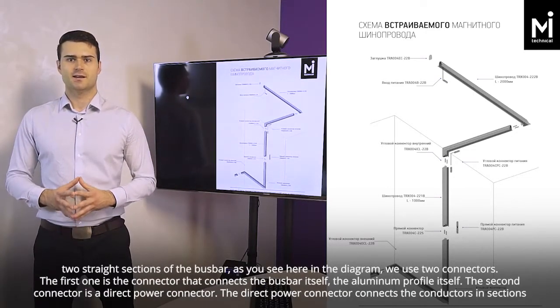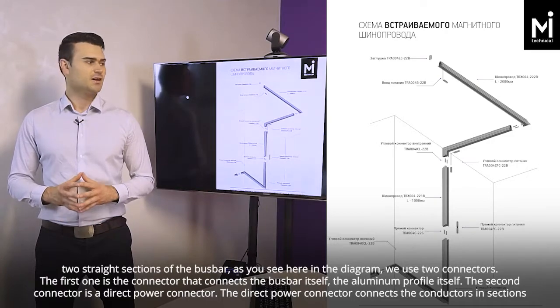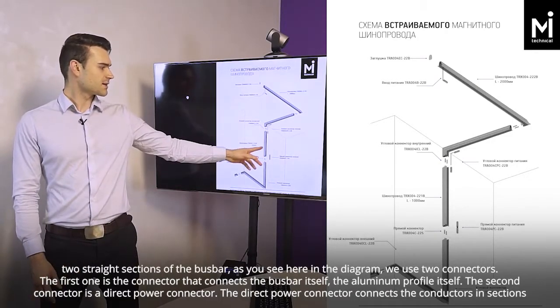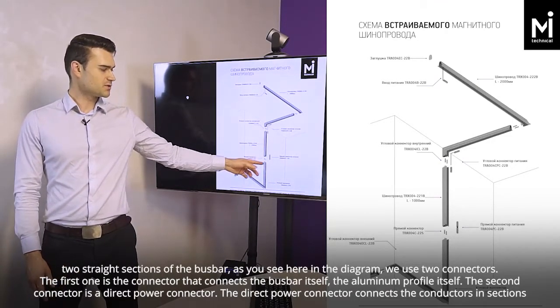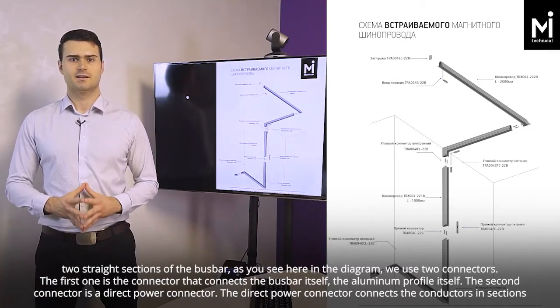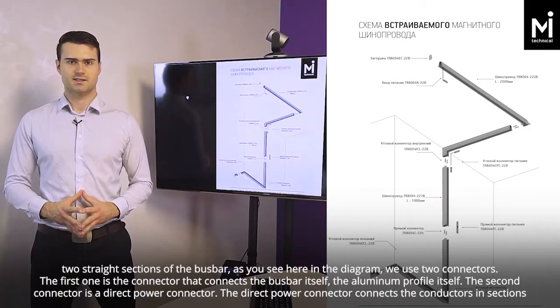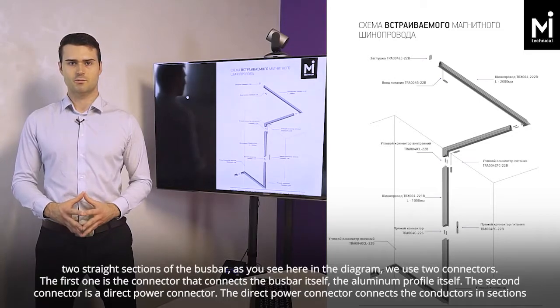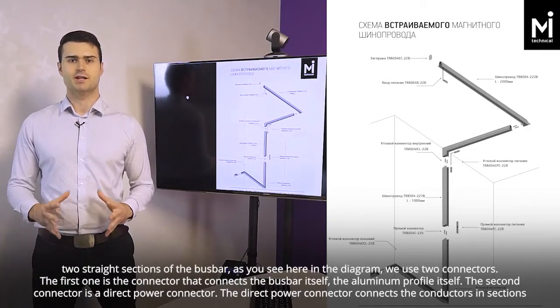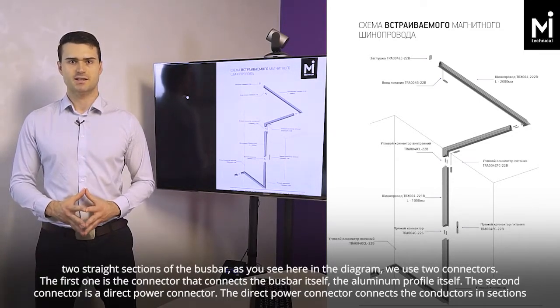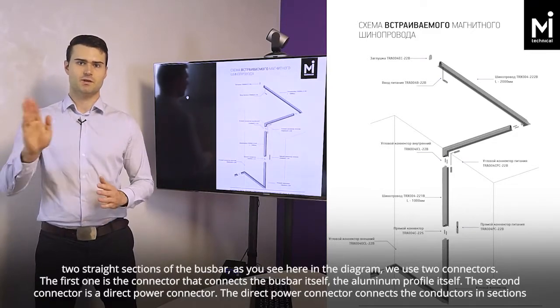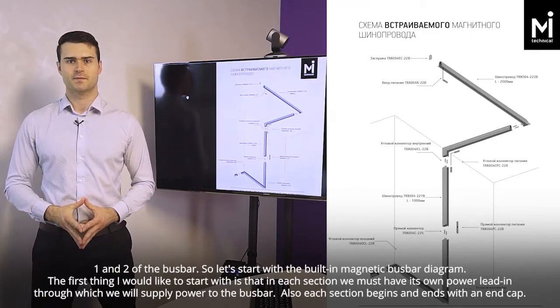To connect 2 straight sections of the busbar, as you see here in the diagram, we use 2 connectors. The first is the connector that connects the busbar itself, the aluminum profile. The second connector is a direct power connector, which connects the conductors in sections 1 and 2 of the busbar.